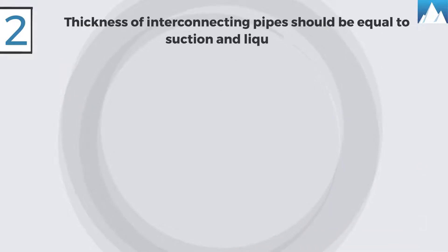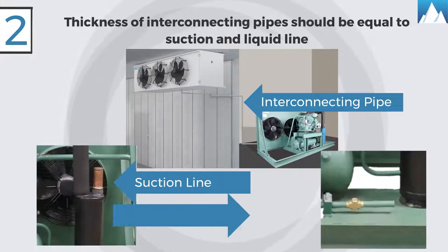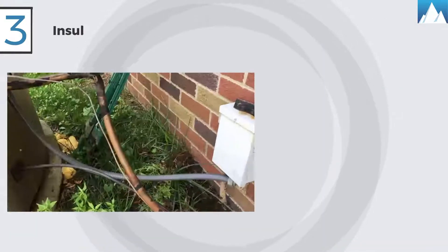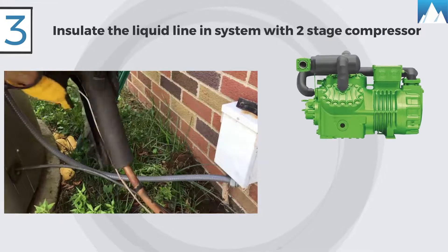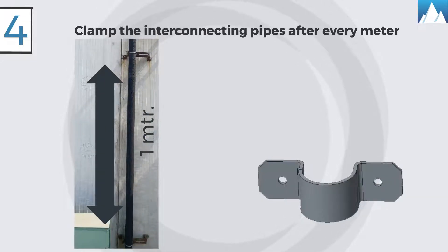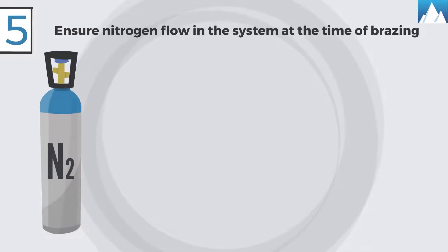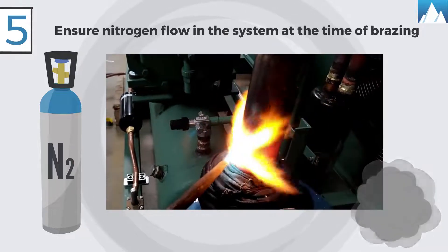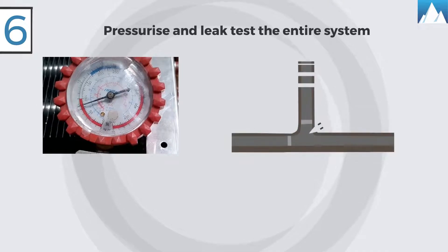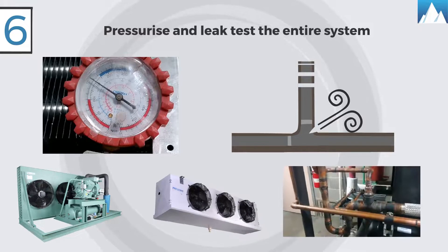Installation procedure: One, avoid material entering into the system while cutting tubes. Two, the pipe thickness of interconnecting pipes should be equal to the condensing unit suction and liquid line. Three, insulate the liquid line if there is a two-stage compressor in the condensing unit. Four, clamp the interconnecting pipes at a distance of every one meter. Five, ensure nitrogen flow in the system at the time of brazing to avoid deposit of carbon inside the pipeline.